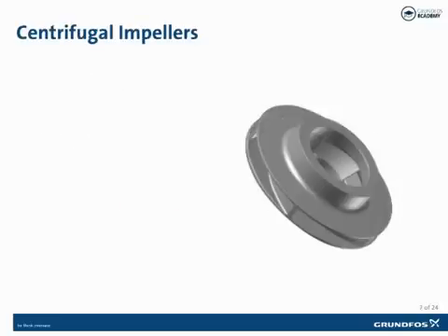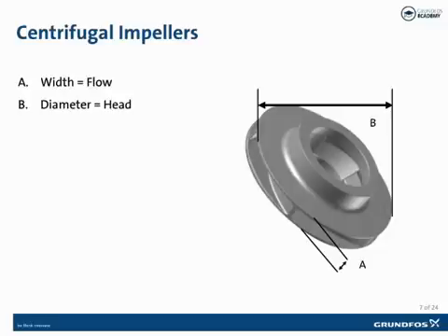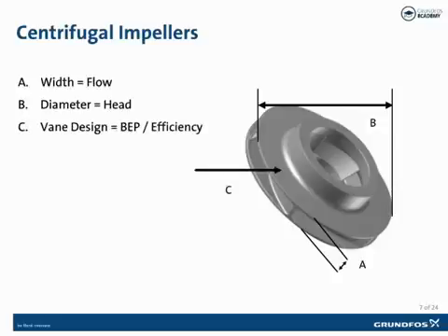The design of the impeller is very important. The width of the cross-sectional area of the vanes is the major determining factor of the amount of flow produced by the impeller. The diameter of the impeller is the major determining factor of the amount of head or pressure that can be produced. And the vane shape is the major influence on the impeller's performance or efficiency.